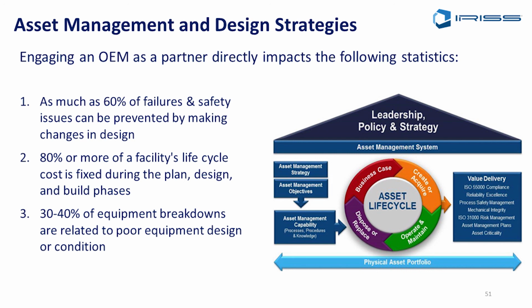It's important from a design perspective to work with your original equipment manufacturer. If you're buying new transformers, switchgear, motors and everything else, think about how you're going to maintain these assets. How are you going to perform condition-based assessments, and can you design in the means and methods to do that safely and efficiently at procurement time? Because 60% of failures and safety issues can be reduced by making changes in the design, and 80% or more of a facility's life cycle costs are also impactable by design.